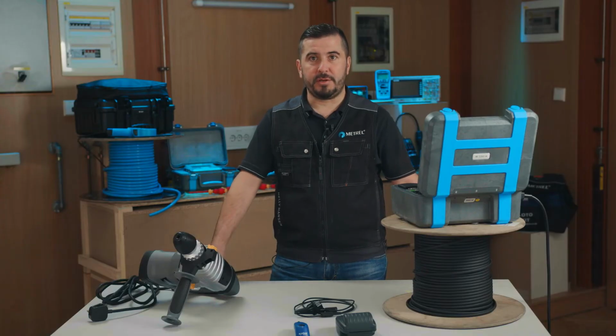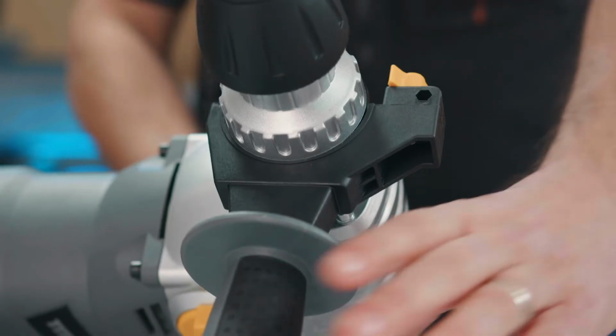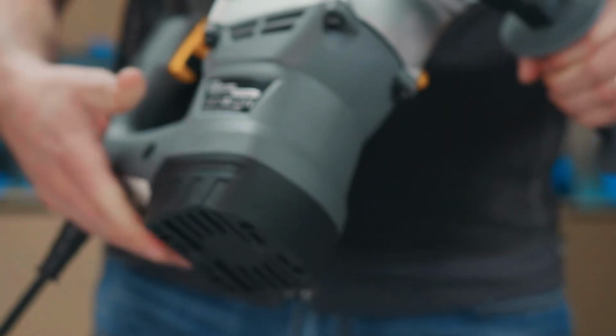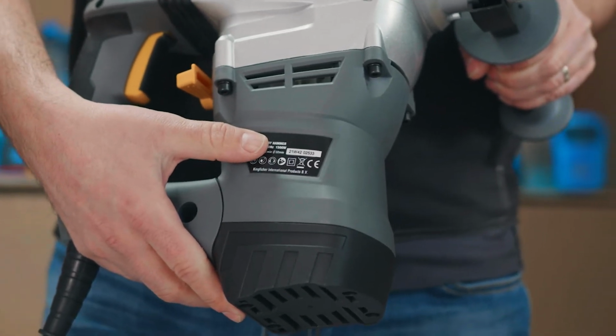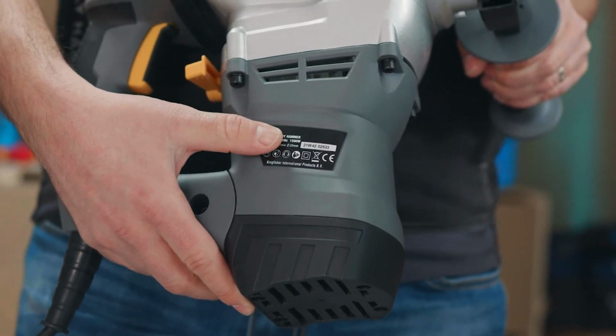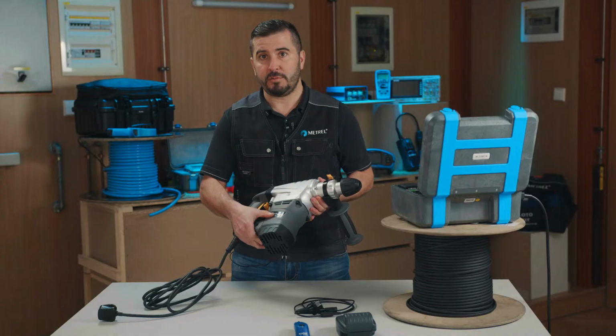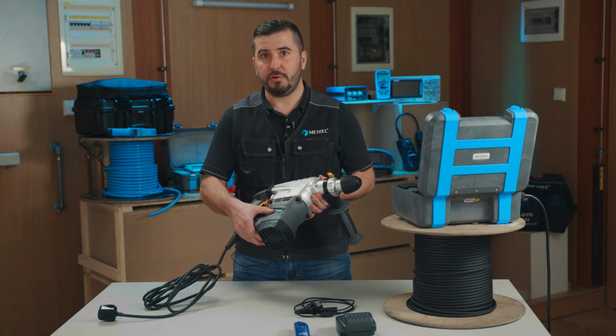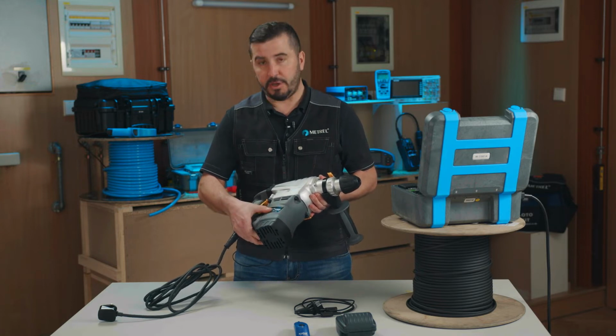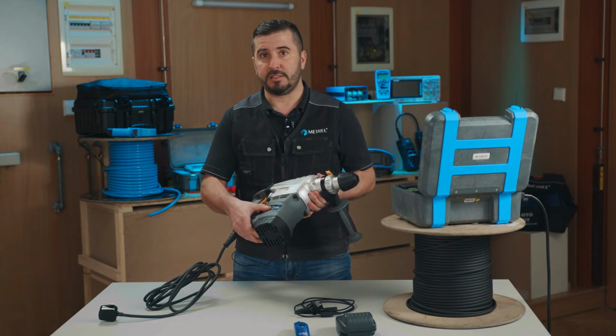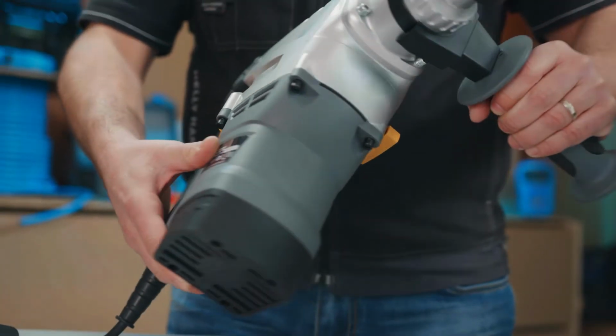If we want to fully examine and test a rotary hammer, we first have to determine which parts will be subject of test and which tests will be used for electrical examination. So, from the rating plate of this appliance, we can see that this is a genuine class 2 appliance. This tells us the small double square symbol, which stands for double insulation and means we have no connection to protective earth. So, as we now know that the appliance is double insulated, we know that the protective earth test will not be applicable.